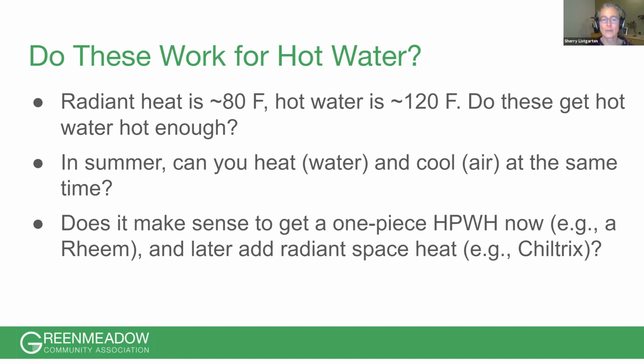Okay, so it's getting there, you're saying. It has been a problem, but it might be getting addressed now. Although I guess what you're saying is the heat pump can't do the floor and the tank at the same time. It does one and then it does the other. So in the case of the Chiltrix, when there's a call for domestic hot water, there's a demand. It will go to like 131 or 133 degrees to prioritize, and it leaves the space heating or cooling for a certain period of time, which is about 15 minutes.